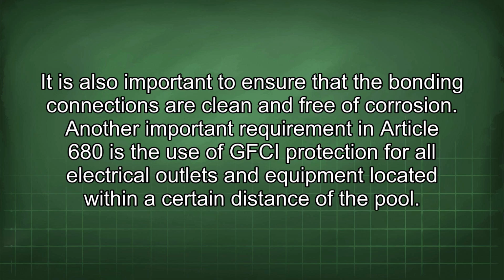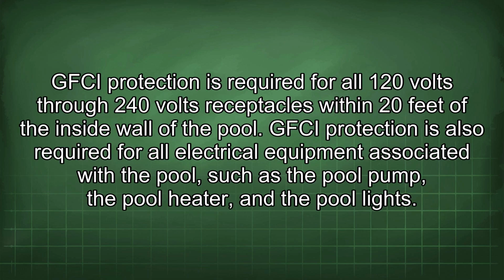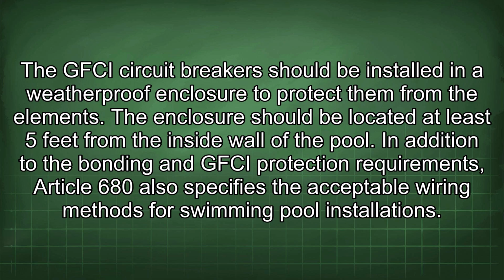Another important requirement in Article 680 is the use of GFCI protection for all electrical outlets and equipment located within a certain distance of the pool. GFCI protection is required for all 120 volts to 240 volts receptacles within 20 feet of the inside wall of the pool. GFCI protection is also required for all electrical equipment associated with the pool, such as the pool pump, the pool heater, and the pool lights. The GFCI circuit breakers should be installed in a weatherproof enclosure to protect them from the elements. The enclosure should be located at least 5 feet from the inside wall of the pool.